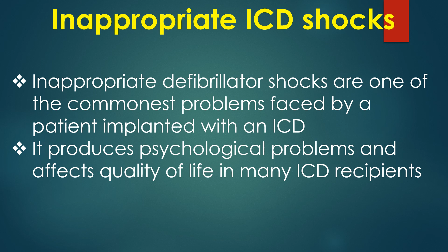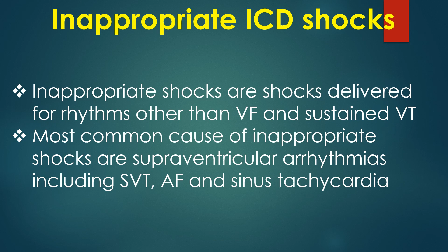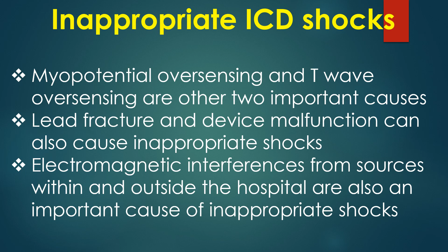Most common cause of inappropriate shocks are supraventricular arrhythmias including supraventricular tachycardia, atrial fibrillation and sinus tachycardia. Myopotential oversensing and T-wave oversensing are other two important causes. Lead fracture and device malfunction can also cause inappropriate shocks. Electromagnetic interference from sources within and outside the hospital are also an important cause of inappropriate shocks. The actual cause in a given case can often be ascertained by ICD interrogation and retrieval of the rhythm prior to the shock which has culminated in the delivery of a shock.